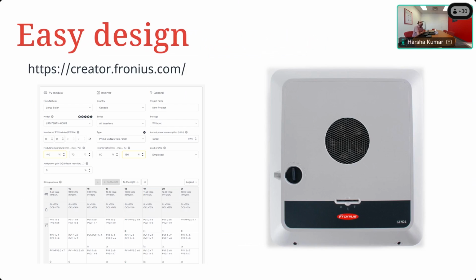But who's to say what the bifacial gain is? That depends on what you plugged in there. Let's say you're saying you don't have any bifacial gains. I'll put it this way: once you plug it in here and you can see the operation of the inverter online, you'll actually get to predict what your bifacial gain is like. But typically your bifacial gain is more of a gray zone, because it's very rare for us to void warranties based on bifacial gains, because it's not something that you can either prove or deny.